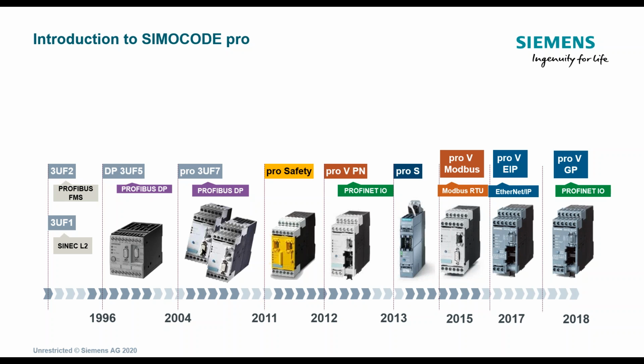In 2004, we redesigned it and we separated the measuring devices. So the SIMOCODE itself is a standalone system. It has a cable that leaves and goes over to the CT and PT, so you're measuring voltage and current if you like. You can do both or just current only. But what we felt is that you're taking this basic unit and putting it into one side of your cabinet where it's just 120 volt or 24 volts, and then the CTs are going over where the 480 is, and you're keeping that side of the cabinet closed so that you just have to wear your standard PPE.